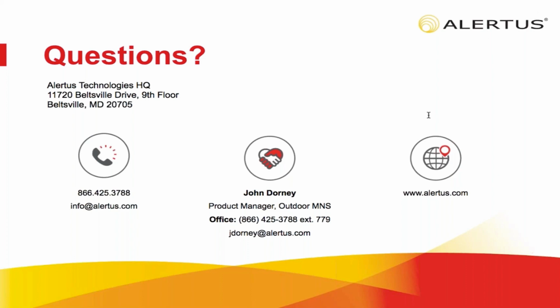How do you test the intelligibility of your system? Okay, so that's a really good question. That's kind of a hot topic in the industry, outdoor intelligibility of systems. There are some companies out there claiming to have processes to tell the intelligibility of your outdoor system. Yes, it's possible, but I tell you, if you have a storm, the wind picks up, you have a drastic temperature change, you have an emergency, the intelligibility is going to change. I think the correct answer to that isn't a quantitative method, but a qualitative method.